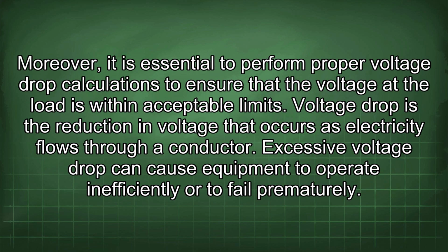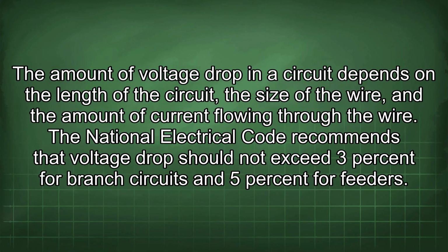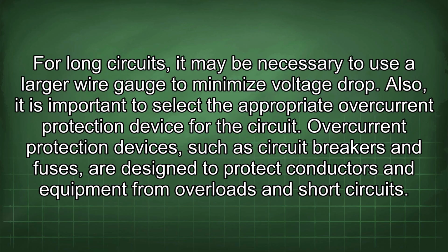Moreover, it is essential to perform proper voltage drop calculations to ensure that the voltage at the load is within acceptable limits. Voltage drop is the reduction in voltage that occurs as electricity flows through a conductor. Excessive voltage drop can cause equipment to operate inefficiently or to fail prematurely. The amount of voltage drop in a circuit depends on the length of the circuit, the size of the wire, and the amount of current flowing through the wire. The National Electrical Code recommends that voltage drop should not exceed 3% for branch circuits and 5% for feeders. For long circuits, it may be necessary to use a larger wire gauge to minimize voltage drop.